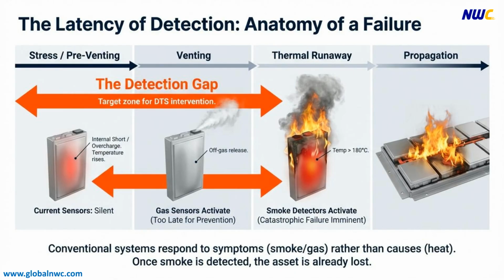By monitoring thermal changes, the root cause rather than the symptom of smoke, in real time, the system enables proactive intervention to stop thermal runaway propagation before it escalates. This capability is the key to achieving true system stability and safety.